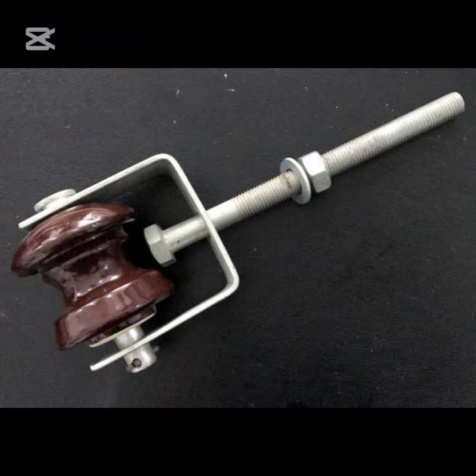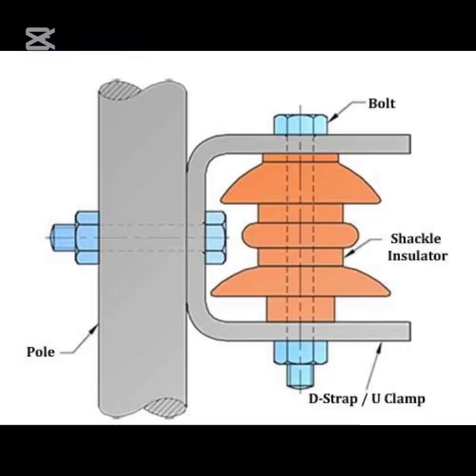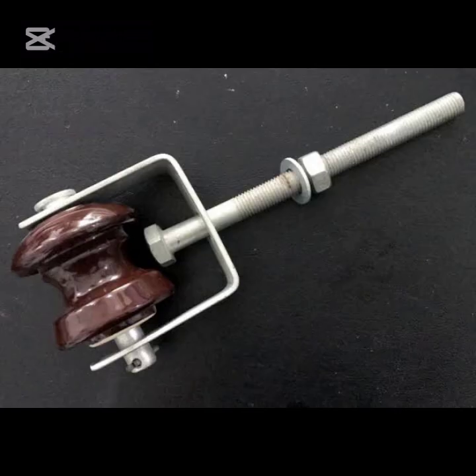Four: shackle insulators. Originally used as strain insulators due to the impact of stress, shackle insulators are now primarily found in low voltage distribution lines. They can be mounted either horizontally or vertically and can be affixed directly to poles or cross arms with bolts. Shackle insulators consist of a ceramic or glass insulator body with strap metal attached to it. The shackle is typically made of a durable metal alloy such as steel or aluminum, designed to securely hold the conductor in place.